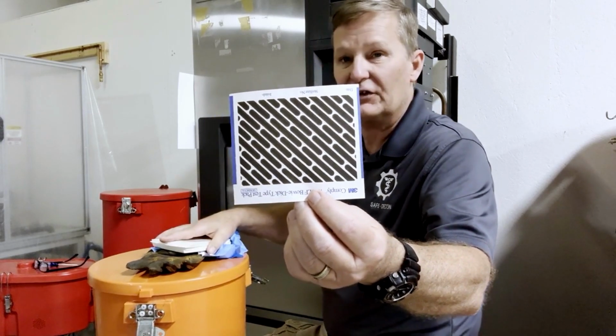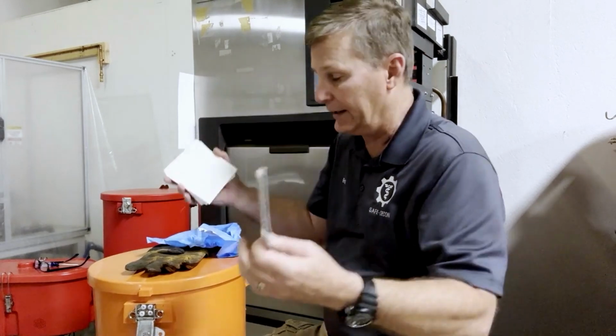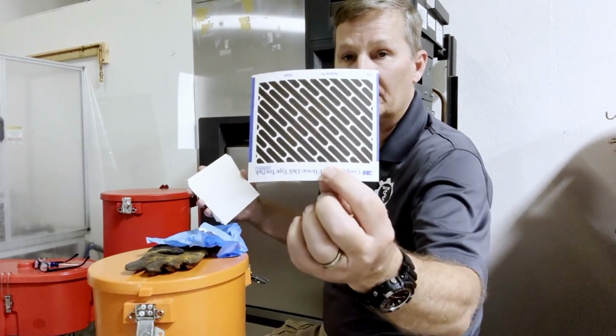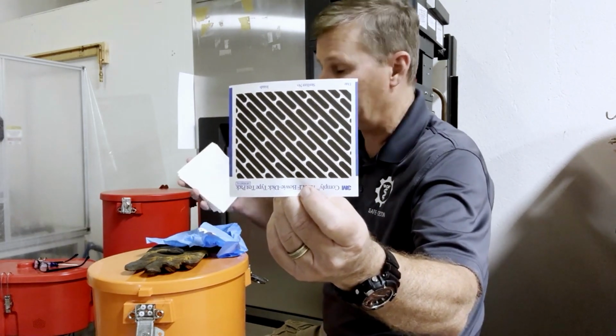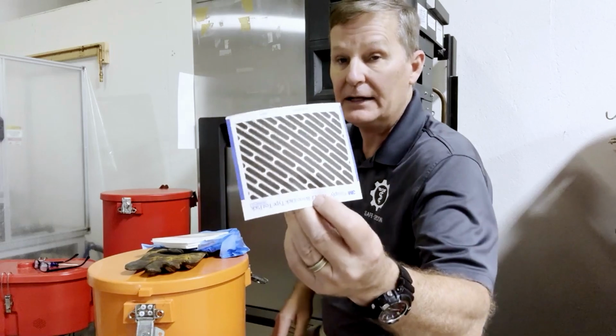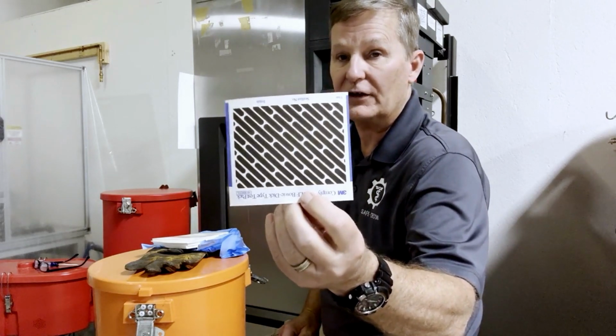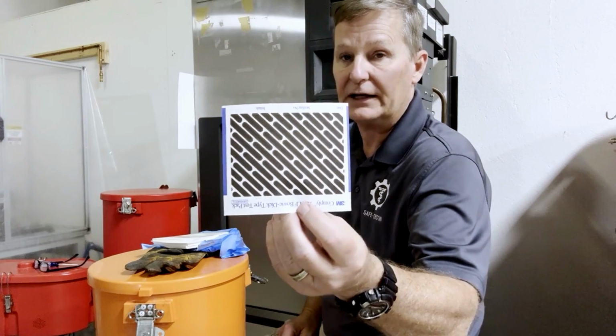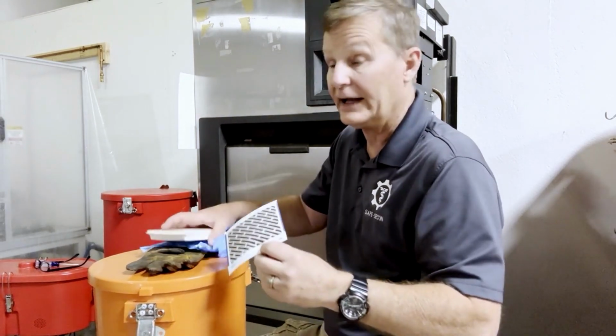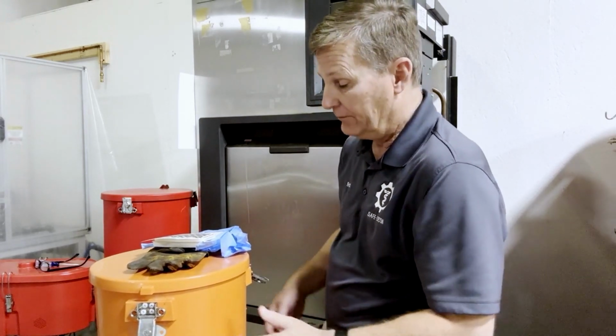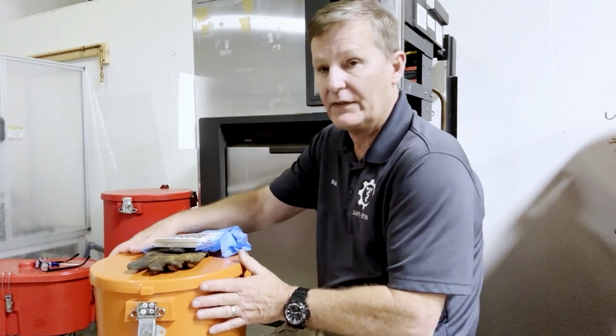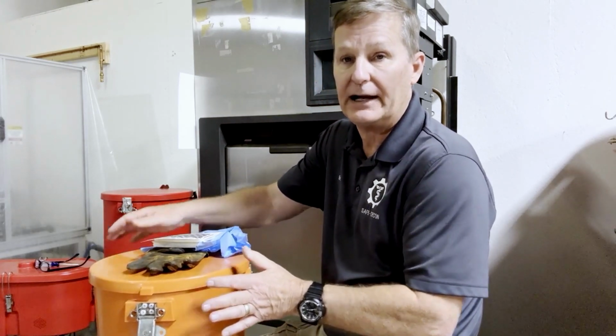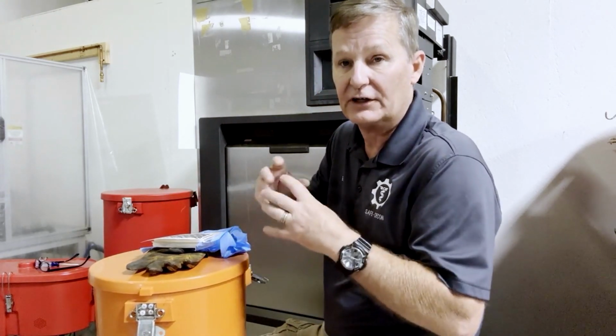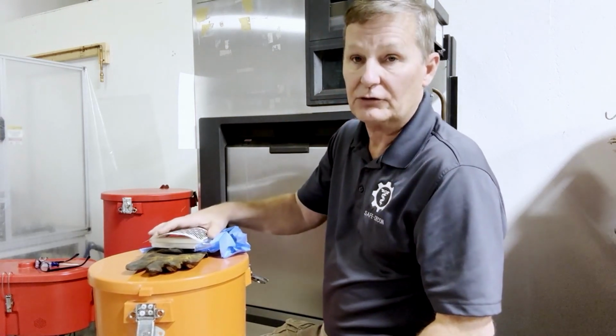Now, what this proves is that even with the Bowie-Dick inside an airtight container, you can achieve the heat and steam penetration on the Bowie-Dick inside of it. And as most of you know, that is a difficult achievement just by getting your autoclave to do it by itself. But to have it in an airtight container, not a bad result there. It does prove that even though they are airtight, we are able to get steam penetration into the contents.